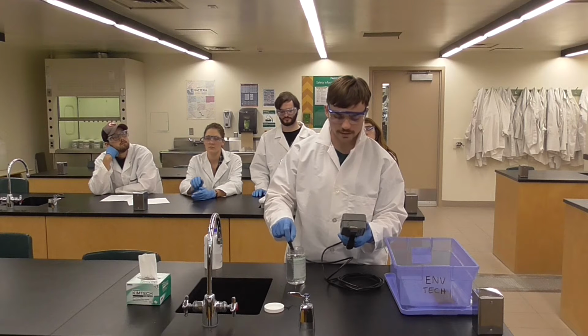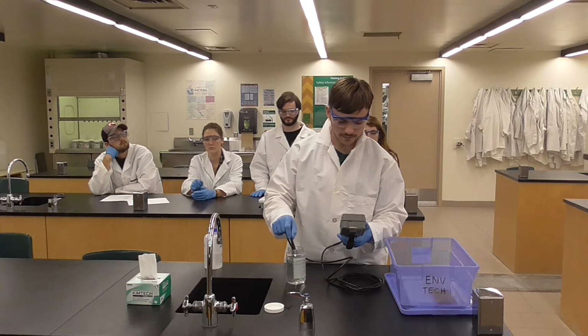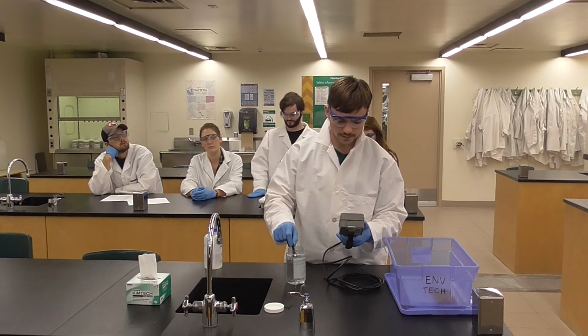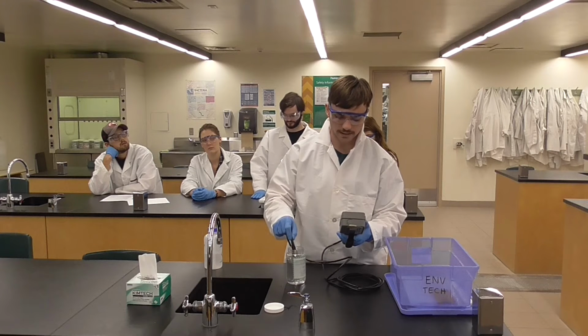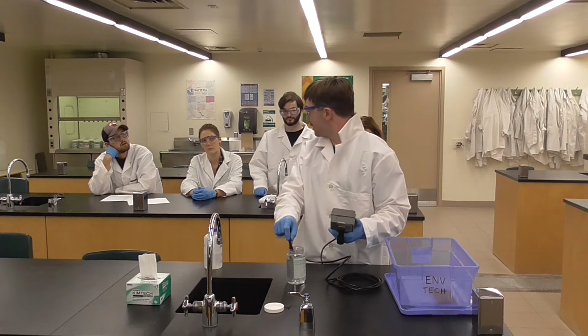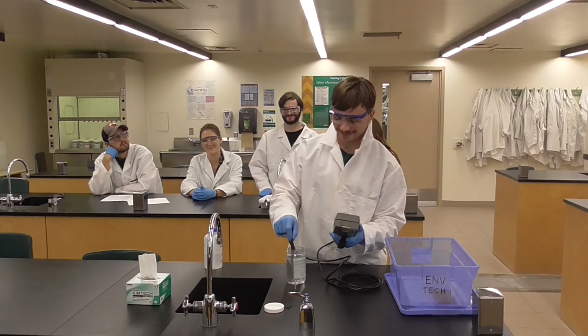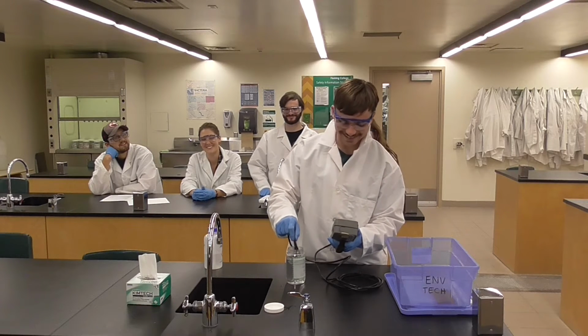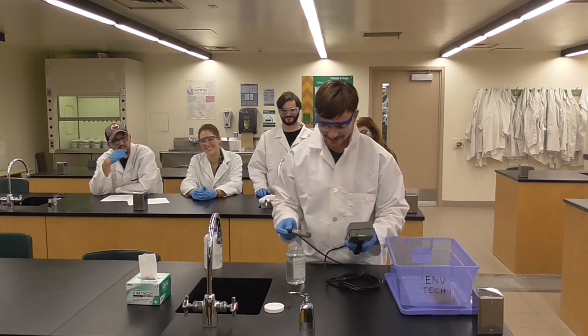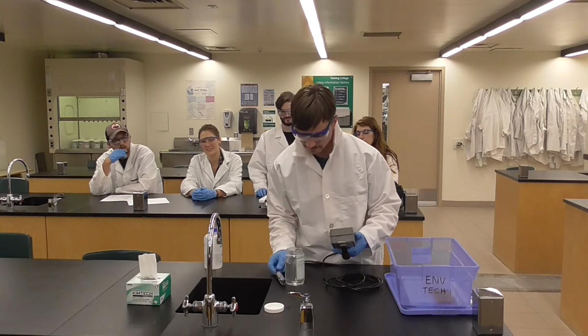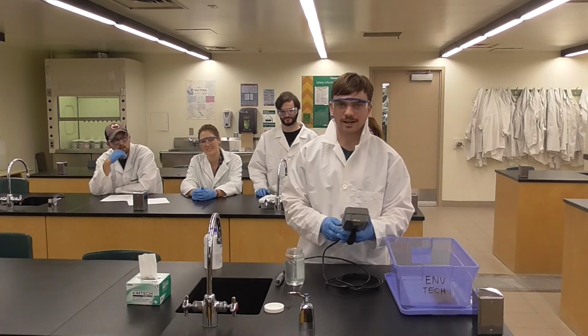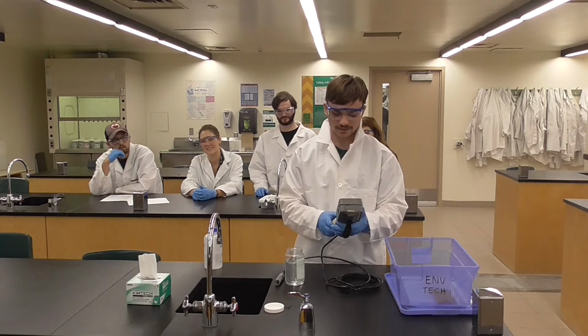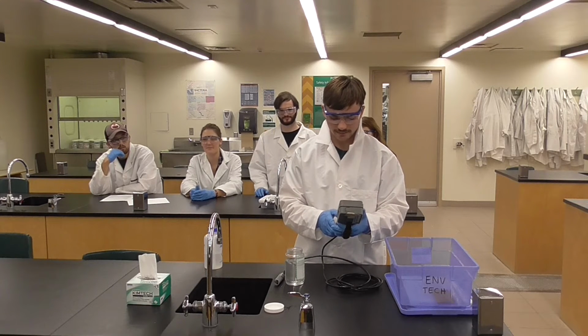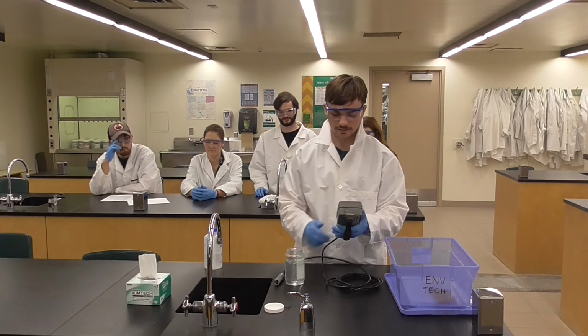My conductivity reading is 462.9 microsiemens per centimeter. Now I'm going to switch my conductivity meter back into specific conductance and measure specific conductivity.